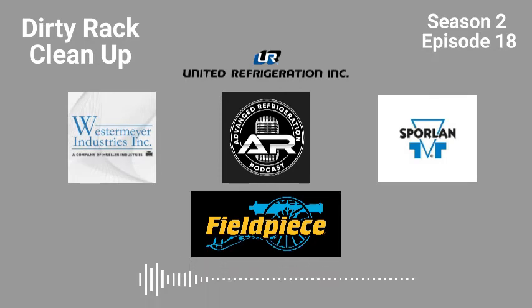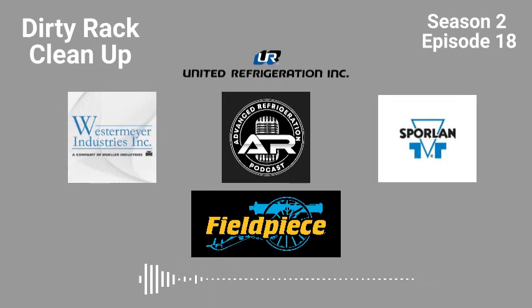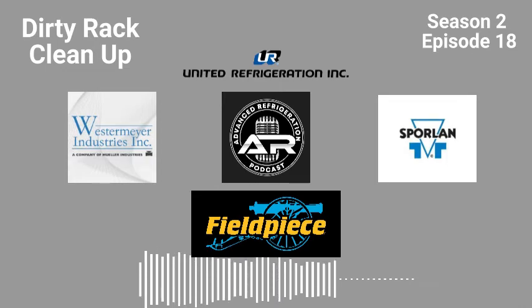I'm done. Yeah, this thing was down, and I tracked it down. When he put it in, I had him disconnect the analog output signal, and then fire it up with just a flash gas bypass valve hooked to it, and that's it. As soon as he started to program it, it smoked. So we tracked it down to the flash gas bypass valve backfeeding DC power through the stepper valve somehow and into the board, shorting it out. So, I mean, that thing was pretty well fucked.